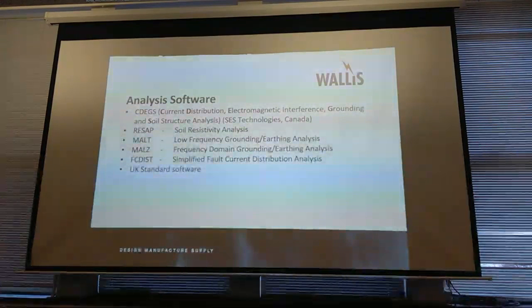Then you've got MALZ, which tends to look at bigger earth electrode systems. I'm talking probably somewhere up in the region of 50 meters. According to the earth mat, it's 0 ohm impedance. In reality, even as good as pure copper is, you will still have impedance in the earth mat. So MALZ does take that into account, and you can do multi-frequency analysis with that. So rather than just 50 hertz, if you've got some funny plant on there kicking out 400 hertz, or military applications that run at 400 hertz, then you could use that to analyze it.